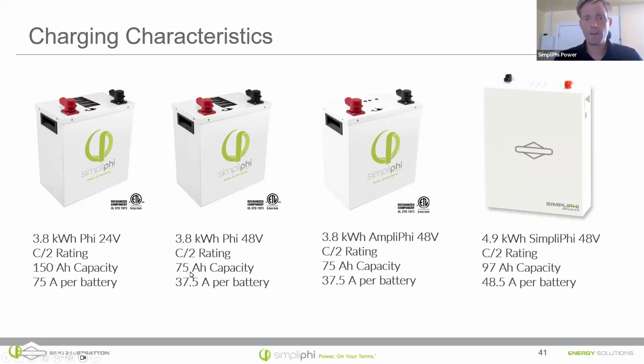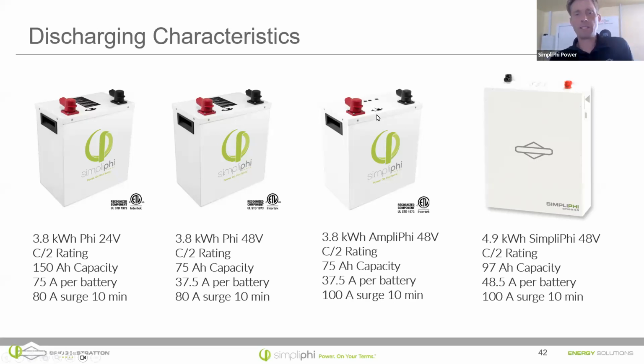So you've got 75 amp hours here. These batteries will charge at a maximum rate of 37.5 amps. So if you have a 150 amp hour battery, C/2 would be half that, or 75 amps per battery. So if you're running 24 volt, you can use higher amperages for charging the batteries. The communicating batteries, the AmpliPHI and the SimpliPhi batteries, are only coming in 48 volt varieties, and a C/2 rating for them would be 37.5 for the 3.8 kilowatt hour AmpliPHI battery, and 48.5 for the 4.9 kilowatt hour SimpliPhi wall mount battery.